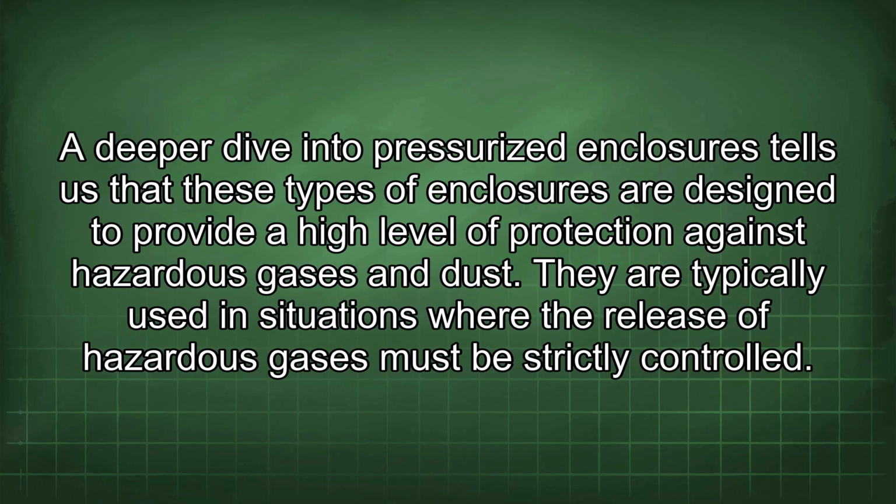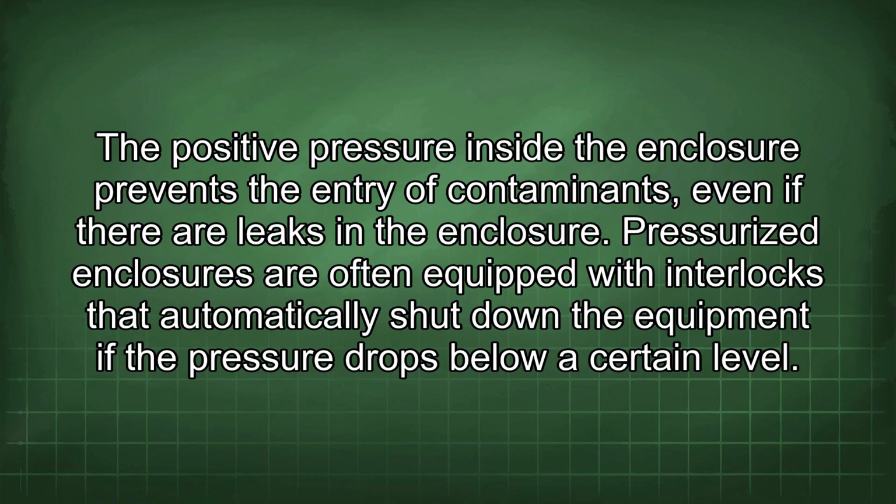A deeper dive into pressurized enclosures tells us that these types of enclosures are designed to provide a high level of protection against hazardous gases and dust. They are typically used in situations where the release of hazardous gases must be strictly controlled. The positive pressure inside the enclosure prevents the entry of contaminants, even if there are leaks in the enclosure.